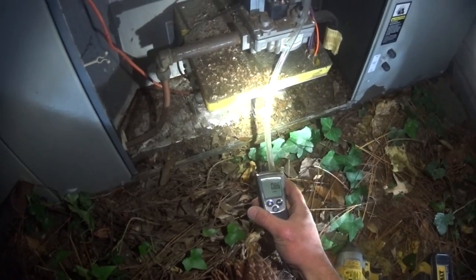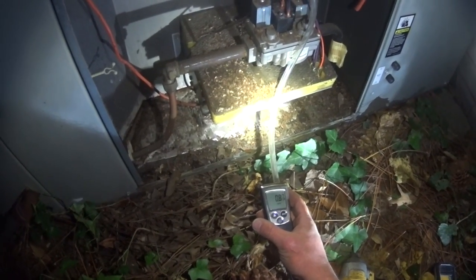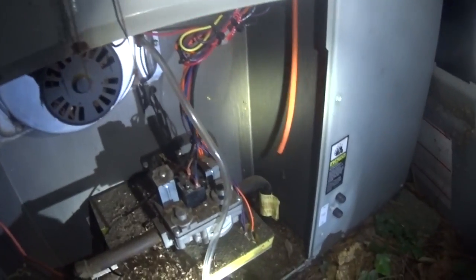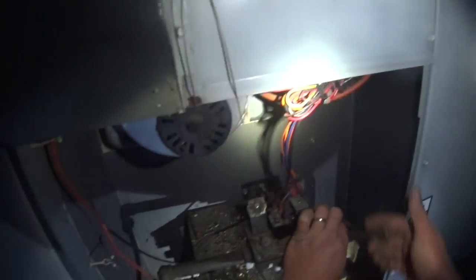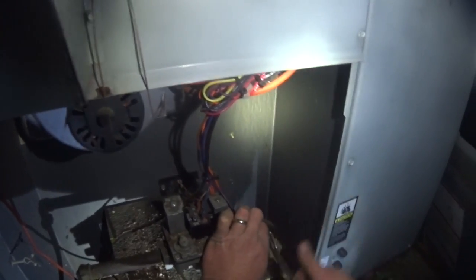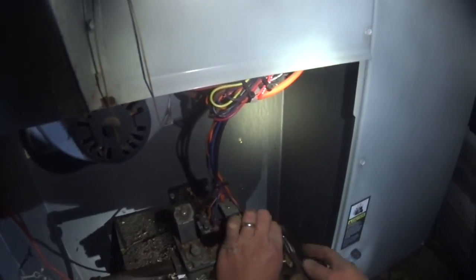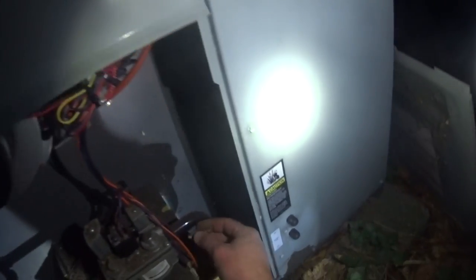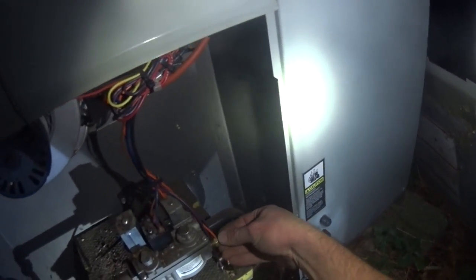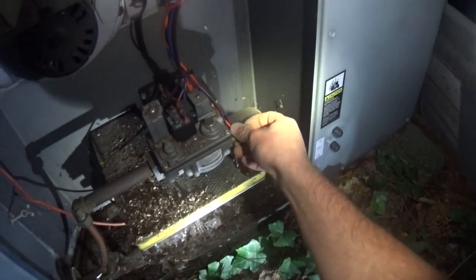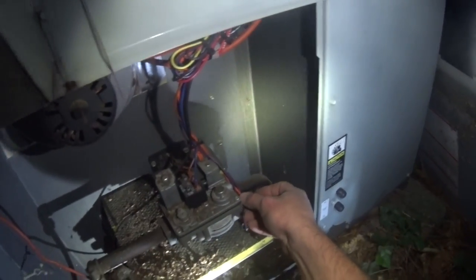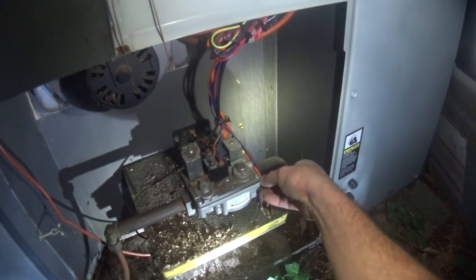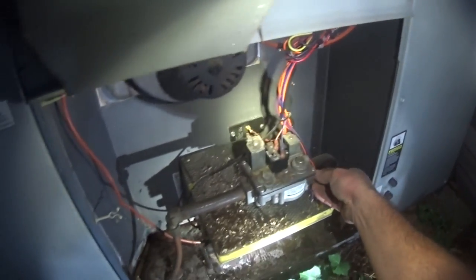We've got almost 0.9 inches of water column on the inducer. My assumption would be that the pressure switch is not actually closing, otherwise the inducer would not continue to run. But we'll get set up for when we do get the inducer to close, or the pressure switch to close. See what we got.